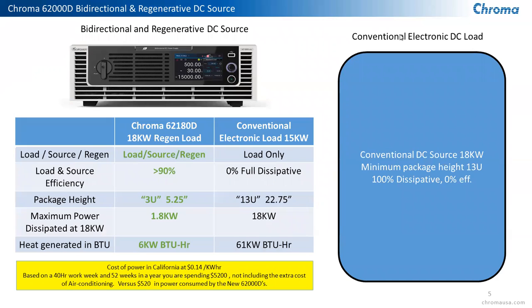The unit also is, because of the efficiency of the unit, when compared to a typical conventional DC load, 90% or greater than 90% efficient. That means that there is only 10% or less power dissipated by the load compared to a conventional load, which is 100% dissipative. It means it dissipates the entire power internally, requires a large heat sink, and it generates a lot of heat.